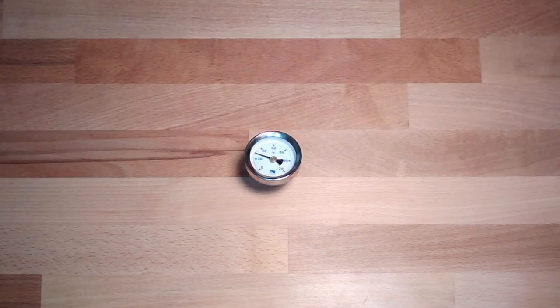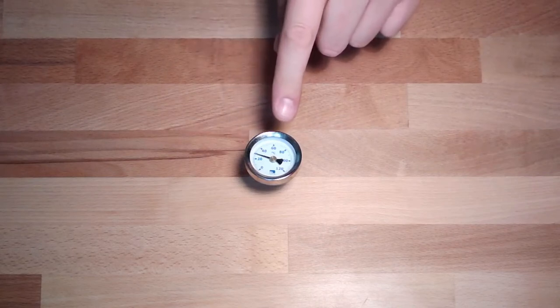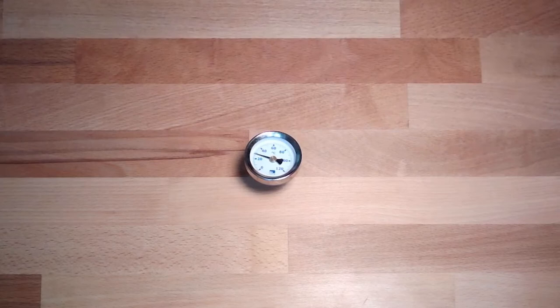This means even if you are at the other end of the hall, you have a look on your measurement wall where all the measurement devices are built in. Usually they are mounted in a cabinet door. They're usually 58 by 58 millimeters large, so 5 by 5 centimeters roughly, or twice as much, or rectangular, a square, whatever. This is the typical measured size of it. Even if you stand at the other end of the wall, you can see in which direction this pointer is showing. Maybe you're not sure if it's pointing to 22 or 23 degrees Celsius in this case, but often it does not really matter.